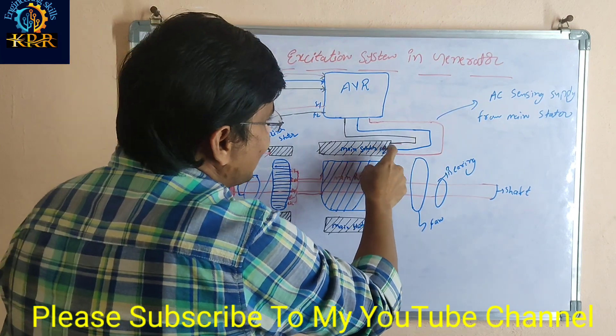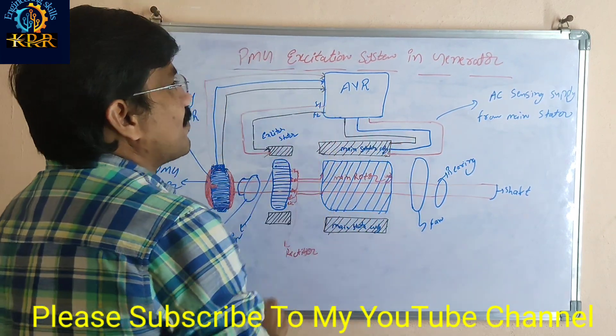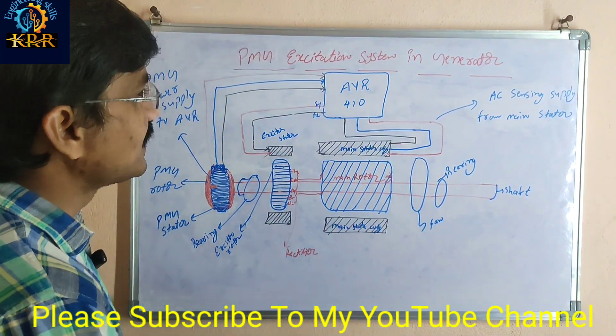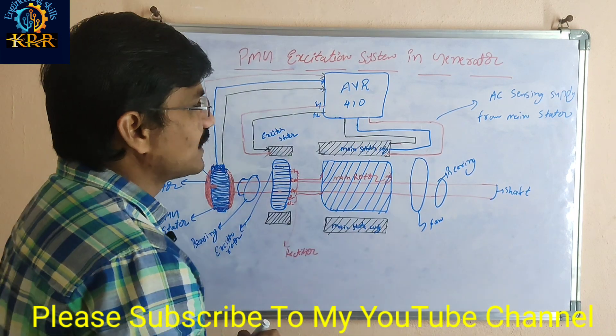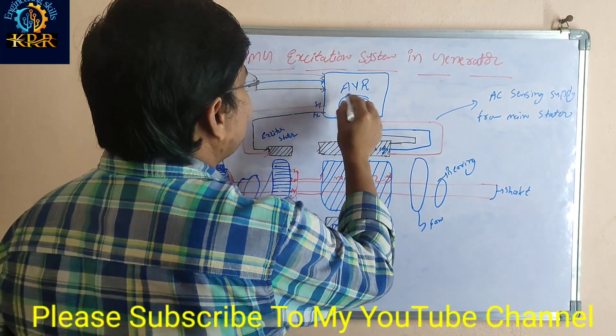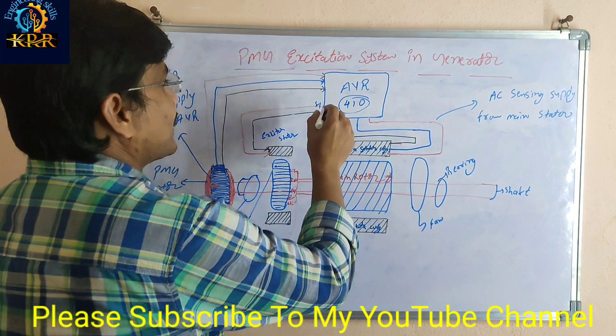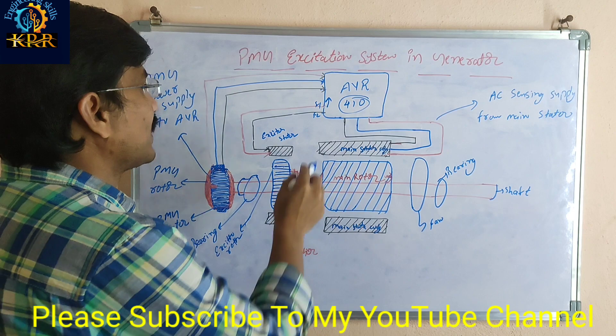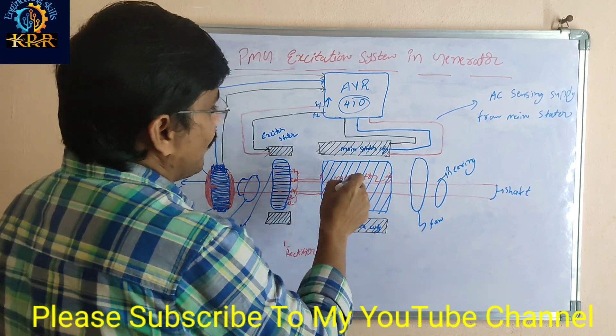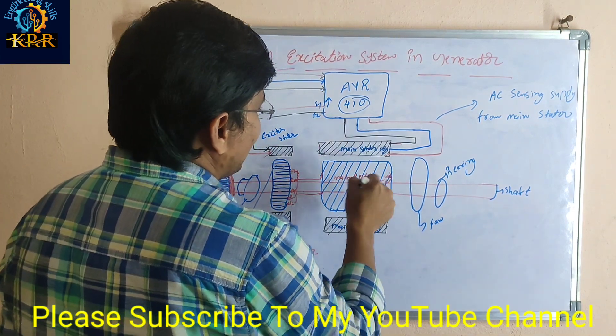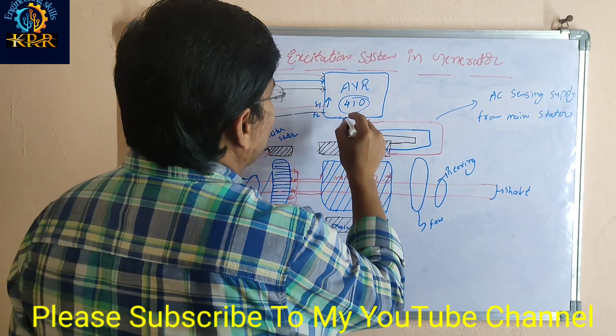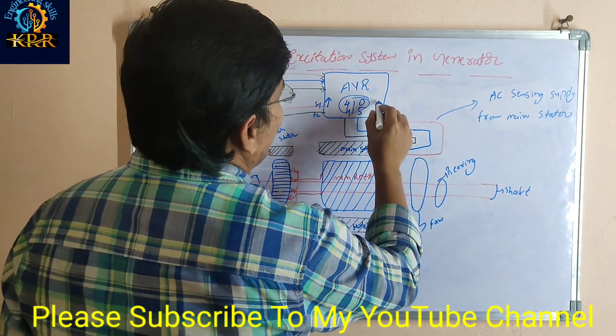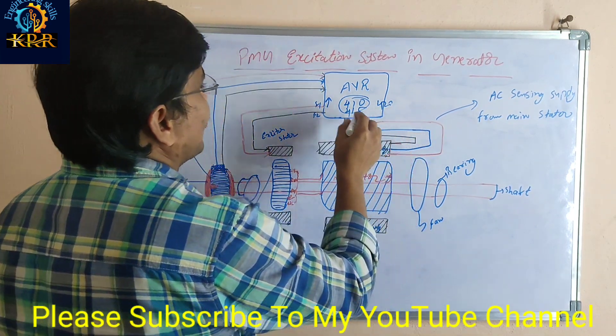The power goes to the load and sensing is also taken from here. If 410 volts is coming, the AVR senses this and applies over-excitation accordingly. With over-excitation, more flux is generated, and the voltage increases — for example, rising to 415 volts.